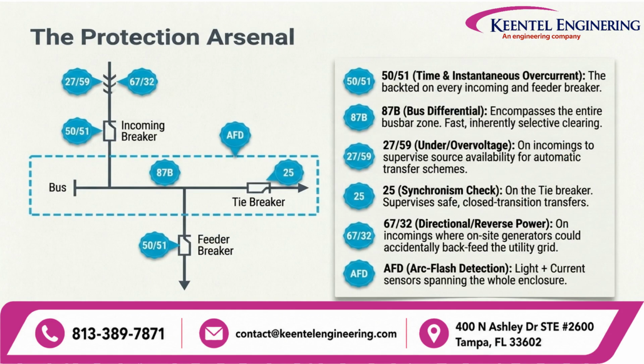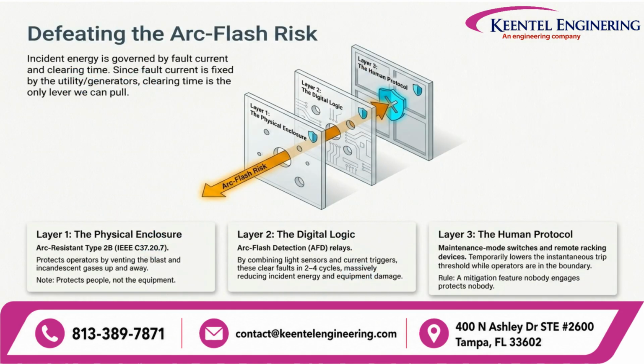A comprehensive protection arsenal includes various elements, from overcurrent and voltage protection to synchronism checks for tiebreakers and arc flash detection. Each component serves a specific, vital role in maintaining system health and safety. Defeating arc flash risk requires a multi-layered approach. This includes the physical enclosure design, digital logic through arc flash detection, and human protocols like maintenance mode switching. Remember, a mitigation feature that no one engages protects no one.